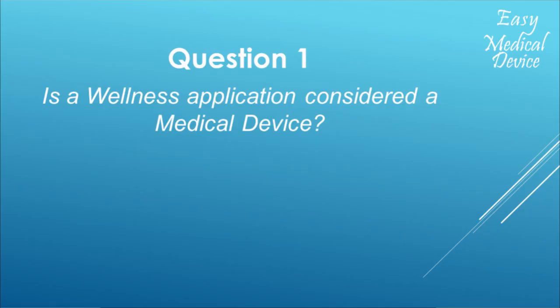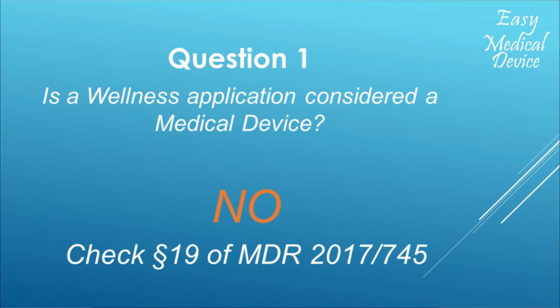What I want to do now is give you a quiz to see if you really understood what is a medical device. Let's talk about software like step trackers, food trackers, or wellness applications on your mobile phone — is this a medical device? Pause the video and think about it. The answer is no, it's not a medical device. To see this clearly in the medical device regulation, go to paragraph 19 — just before the first article — and you will see that those small applications are not considered medical devices.